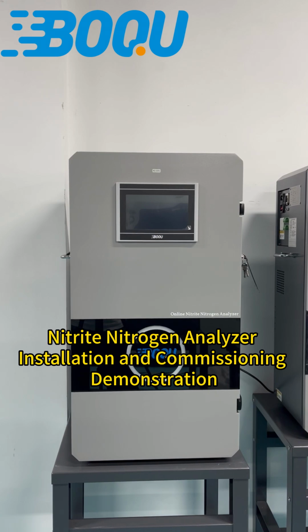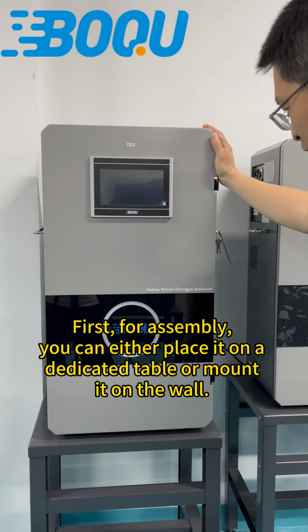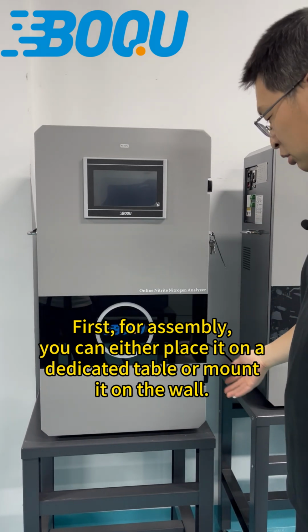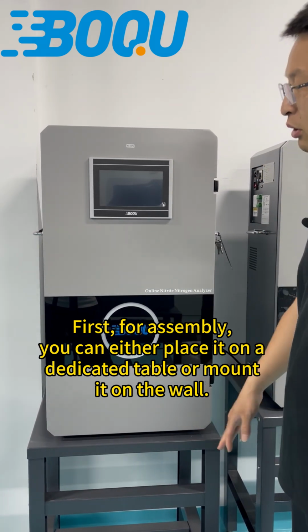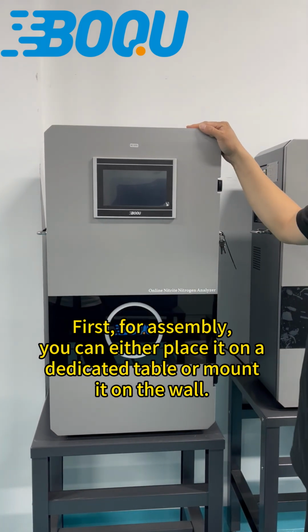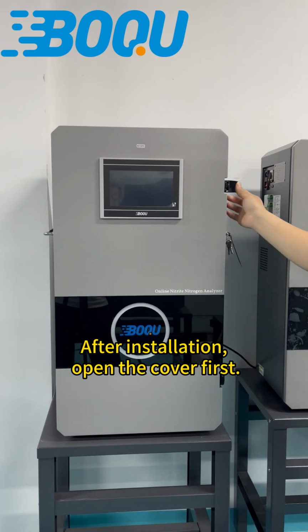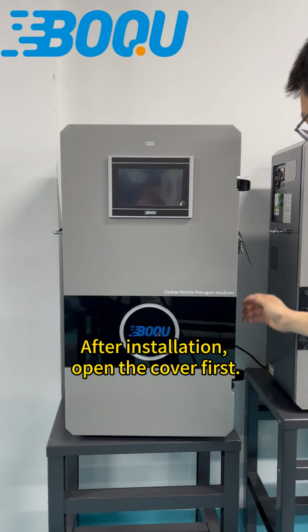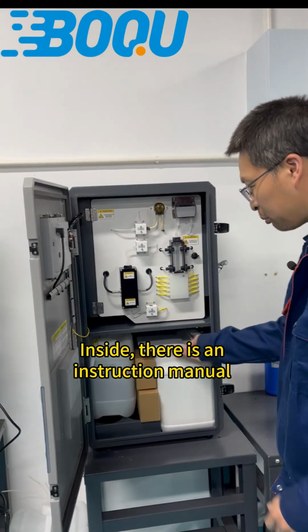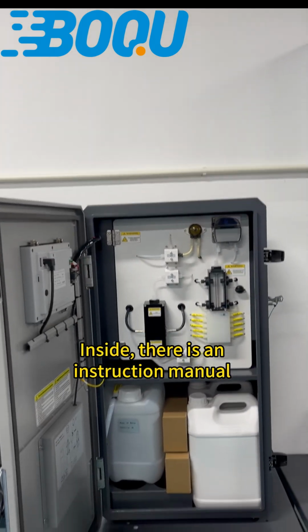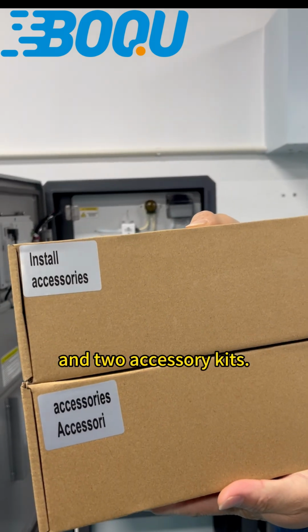Nitrite nitrogen analyzer installation and commissioning demonstration. First, for assembly, you can either place it on a dedicated table or mount it on the wall. After installation, open the cover first. Inside, there is an instruction manual and 2 accessory kits.